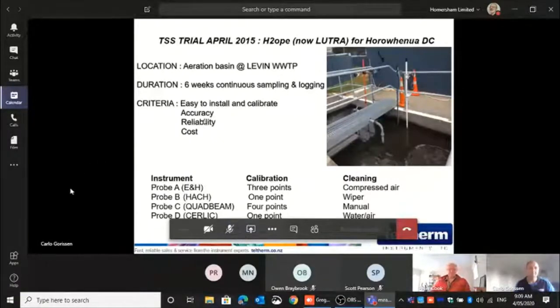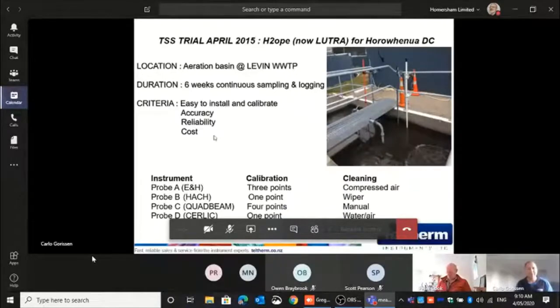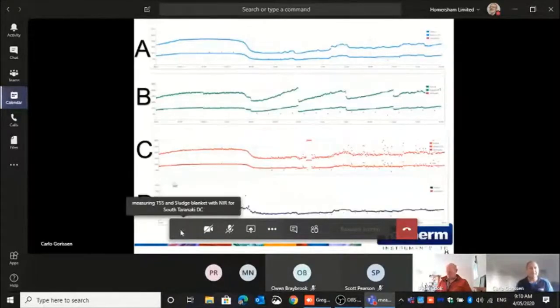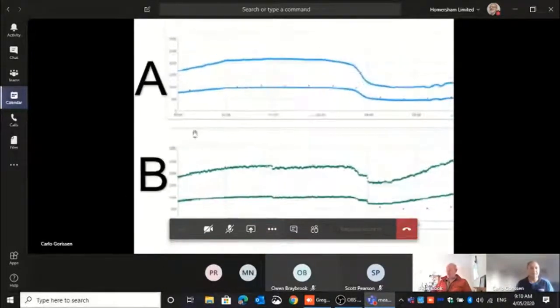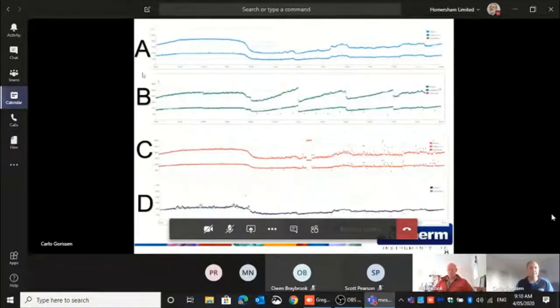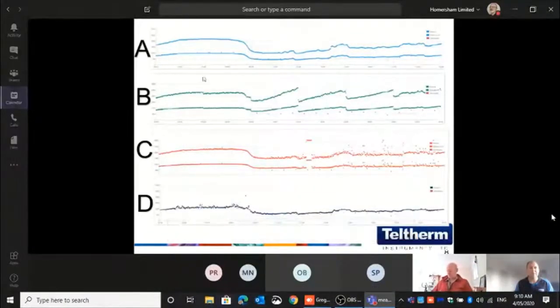Basically, we had an Endress+Hauser, the Hach, a QuadBeam, and our probe in one aeration basin at the same depth, and in the middle was a sampler that took a lab sample every so often. Here you see, if we go a little bit closer, these little red dots are actually the lab samples. So for the Endress+Hauser one, this is the calibration curve.